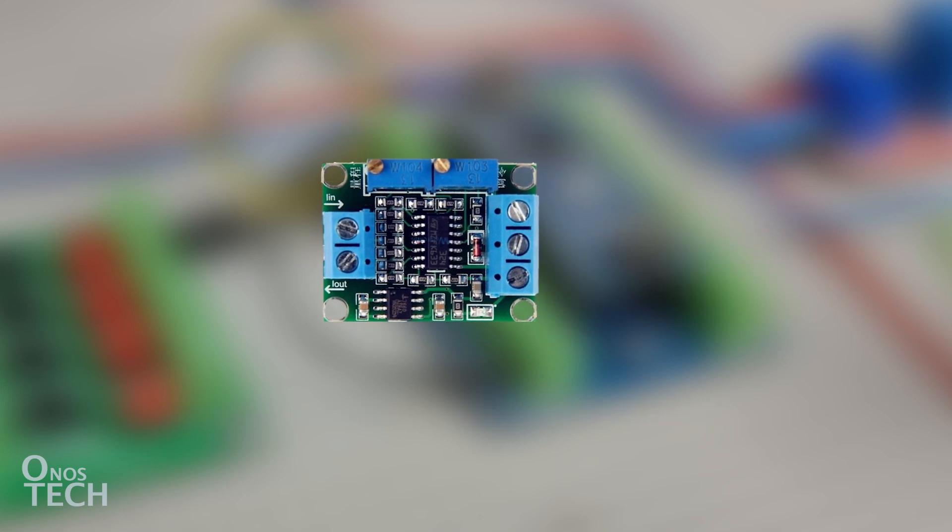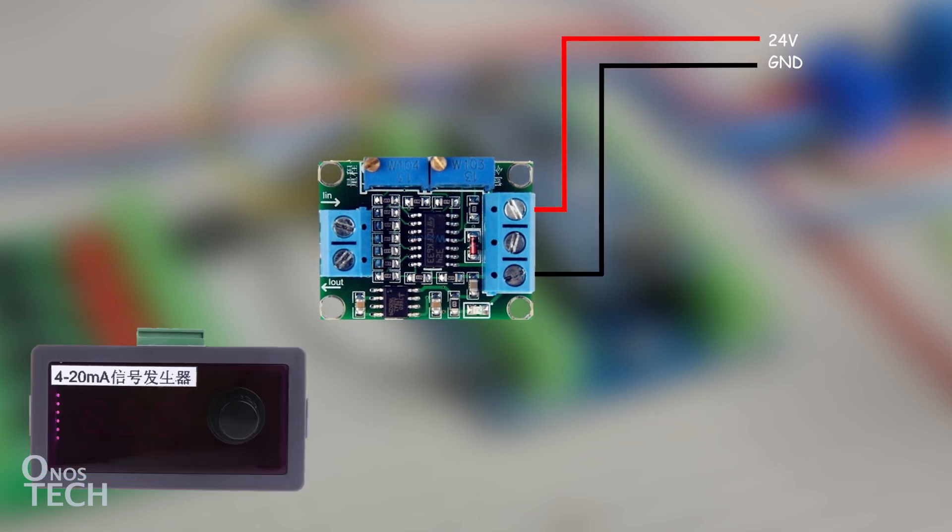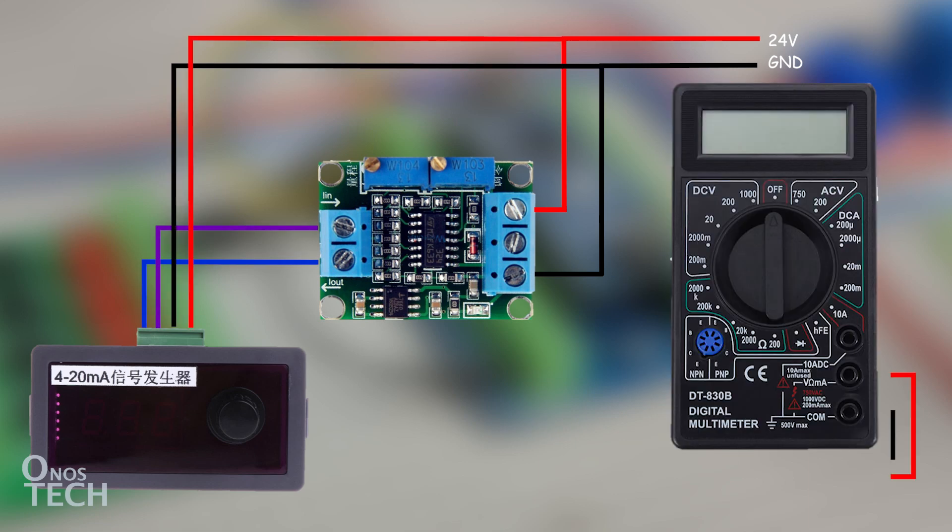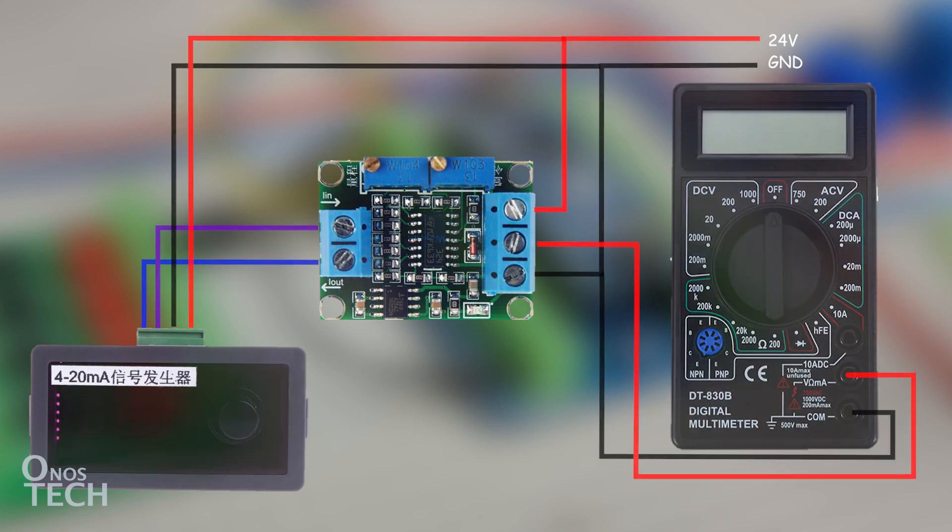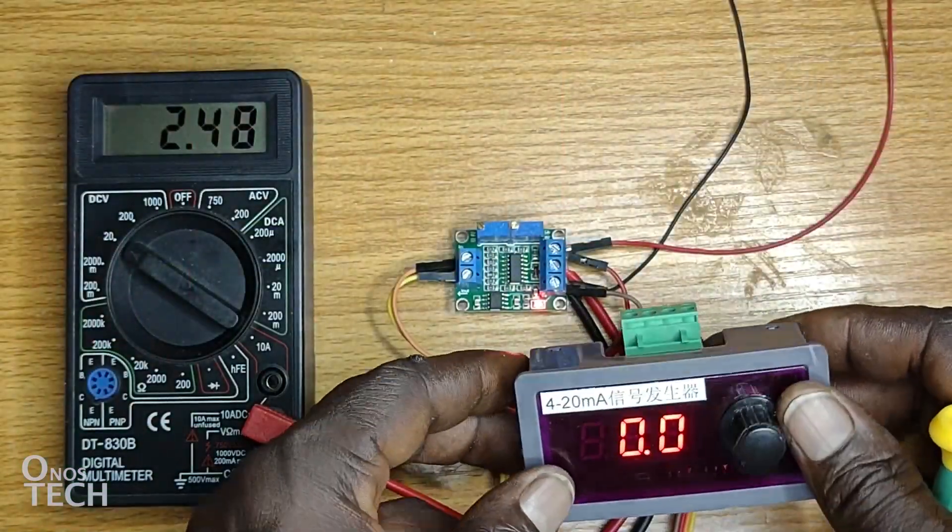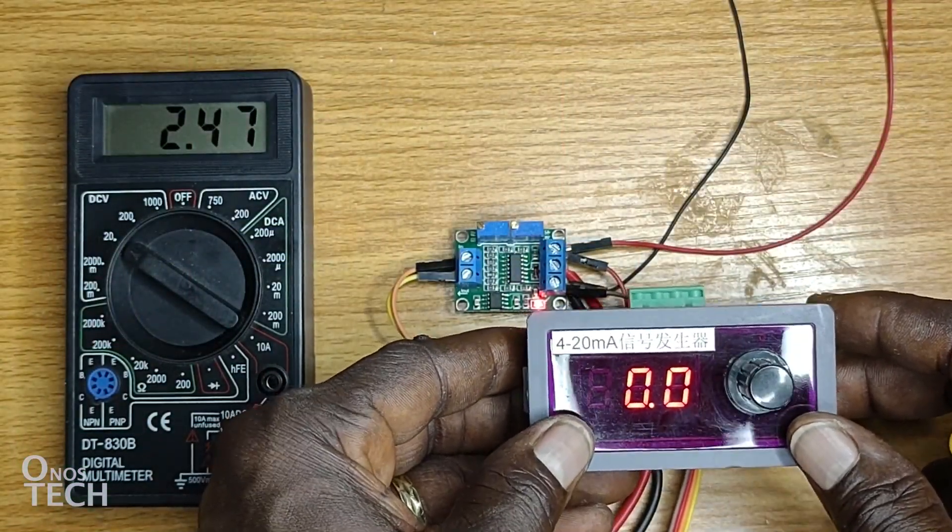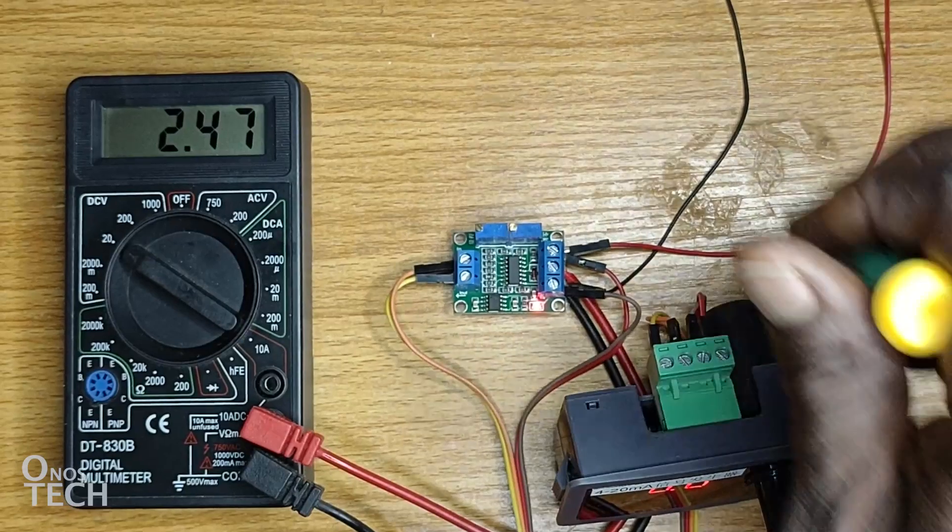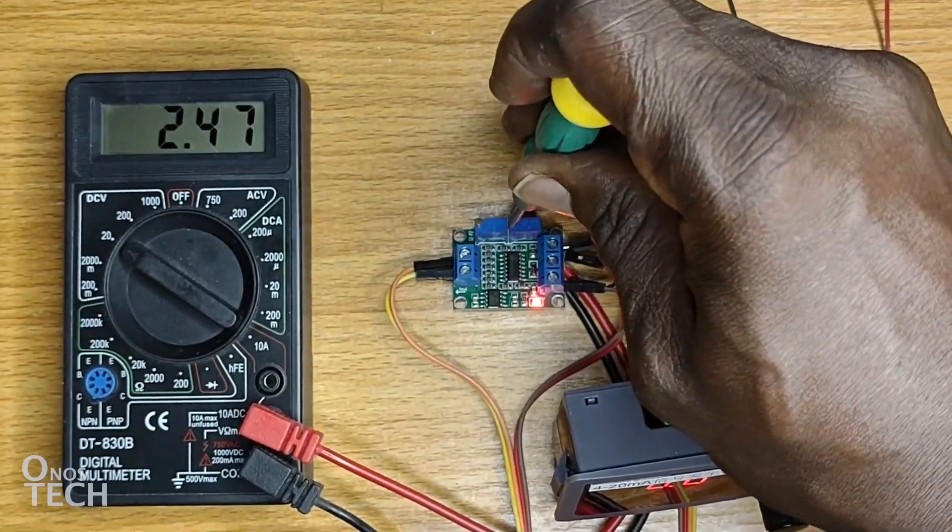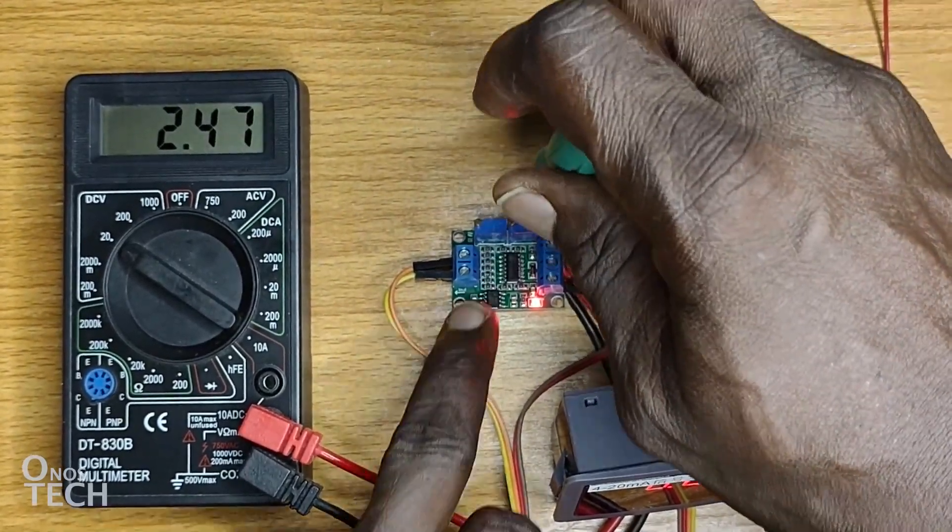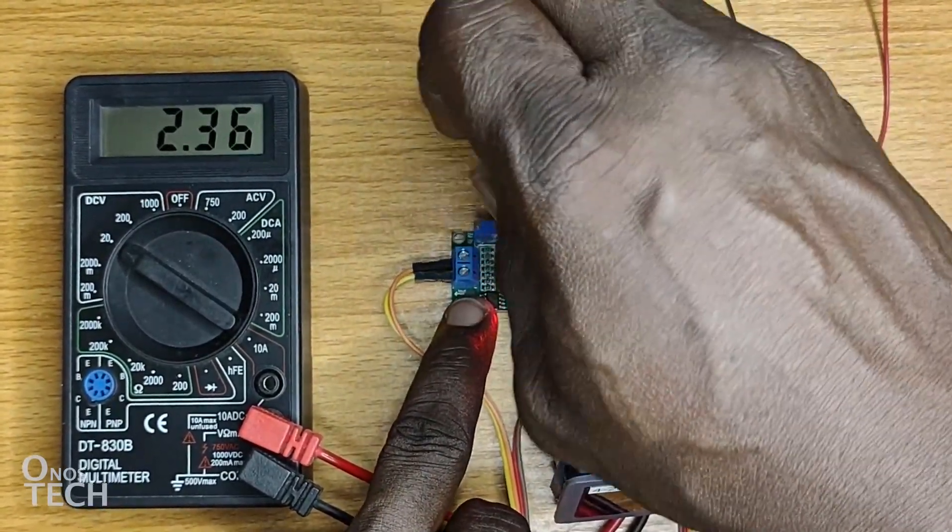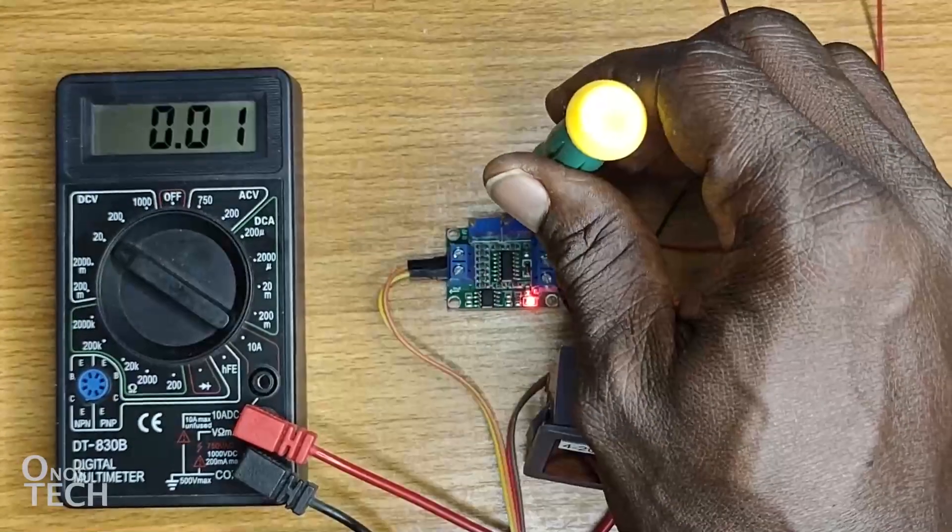Now, set up the connection for the calibration of the module with a 4 to 20 mA current source and a multimeter set to measure voltage. Set the current source to 0%. And, adjust the right potentiometer on the module with a small screwdriver until the multimeter reading is 0.